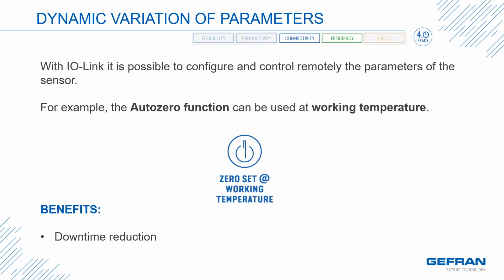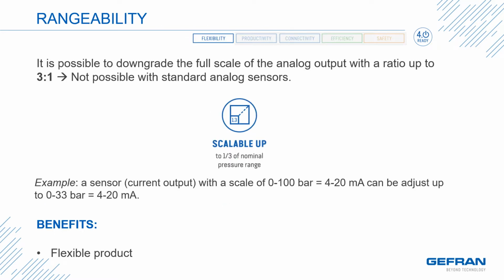With a device on the IO-Link network, it is possible to configure and remotely control the parameters of the sensor. For example, with a melt pressure sensor, the auto zero function can be engaged when the machine is at working temperature. All of Gefran's IO-Link models can be re-ranged with a ratio up to 3:1 down from the full scale of the sensor. For example, a sensor with a scale of 0 to 100 bar can be adjusted to a full scale of 0 to 33 bar. This becomes a great flexibility feature to allow one sensor to be stocked for several possible applications.